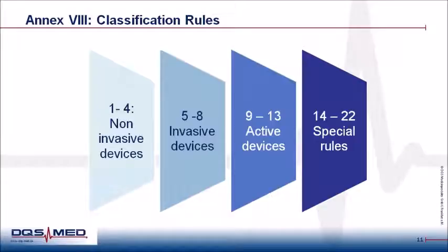Secondly, the MDD contains 18 rules for classification, which can be found in Annex 9 of the MDD. But the new MDR contains overall 22 rules, which is 4 more than the previously published Medical Device Directive. These rules are grouped by the primary application of the medical device, and selecting the applicable rule for a medical device is decisive for the risk classification.